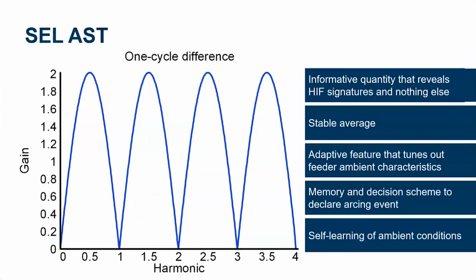The nice thing about using this interharmonic energy is we're going to get rid of that DC and those integer harmonics, where we expect to see, for some of our nonlinear loads, the majority of the current on those devices. We filter all of that out and just look for the stuff in between those integer harmonics. Once we establish a reference and a stable average, we're going to look for deviations from that and deviations from a tuning point in order to detect that harmonic signature associated with arcing on the power system. And when we see that arcing, we're going to be able to indicate whether or not there's a high impedance fault in the system.